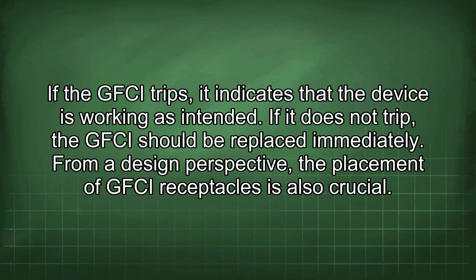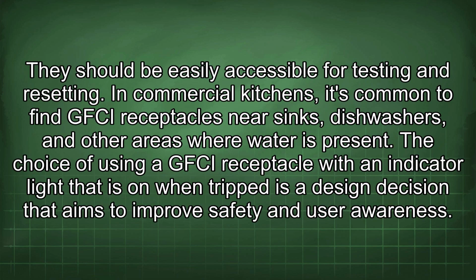From a design perspective, the placement of GFCI receptacles is also crucial. They should be easily accessible for testing and resetting. In commercial kitchens, it's common to find GFCI receptacles near sinks, dishwashers, and other areas where water is present. The choice of using a GFCI receptacle with an indicator light that is on when tripped is a design decision that aims to improve safety and user awareness.